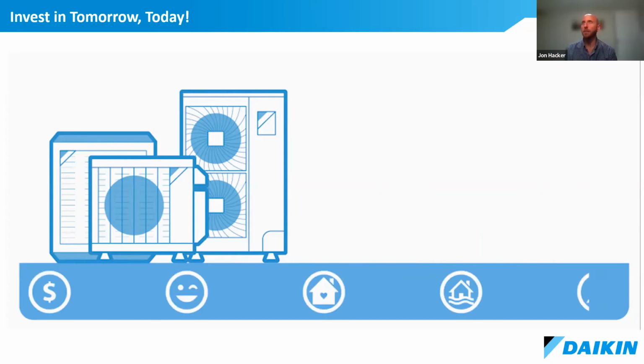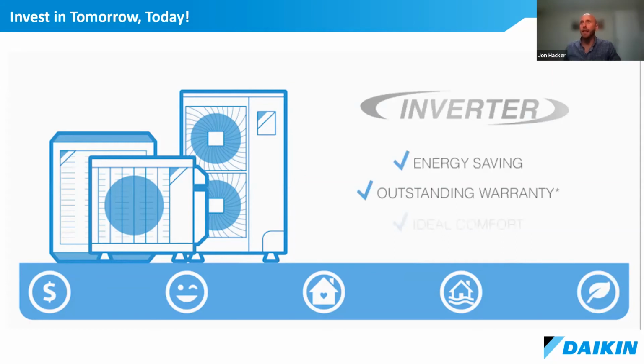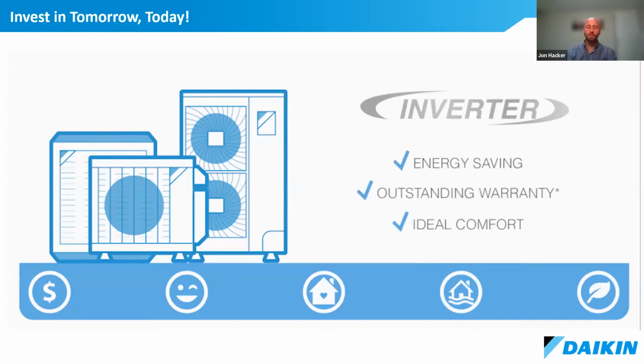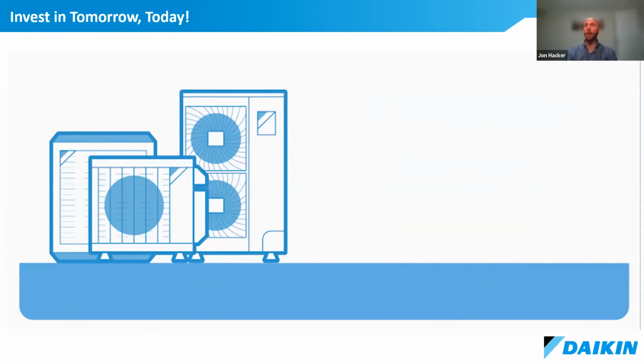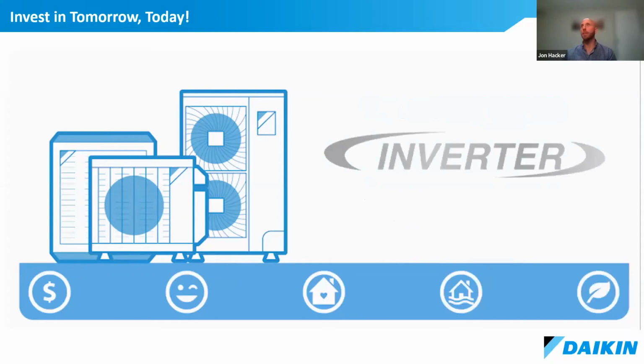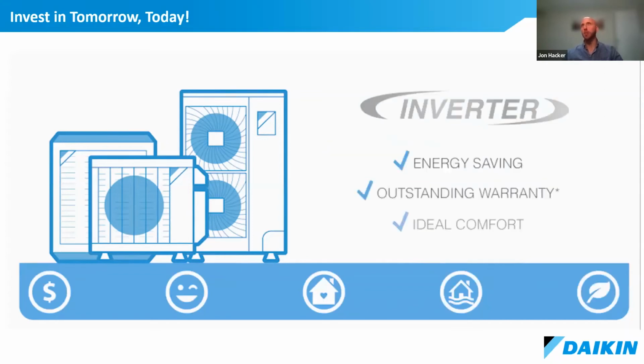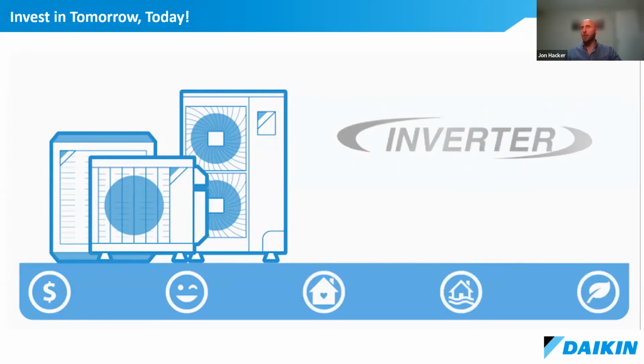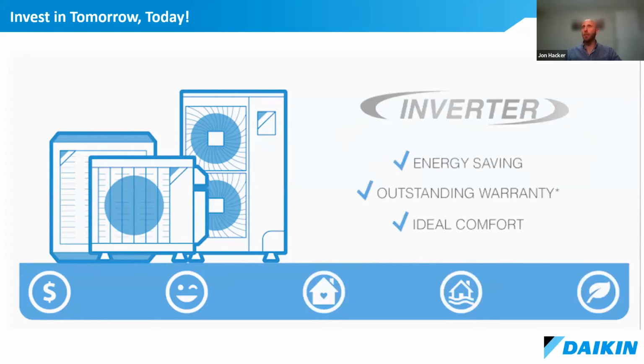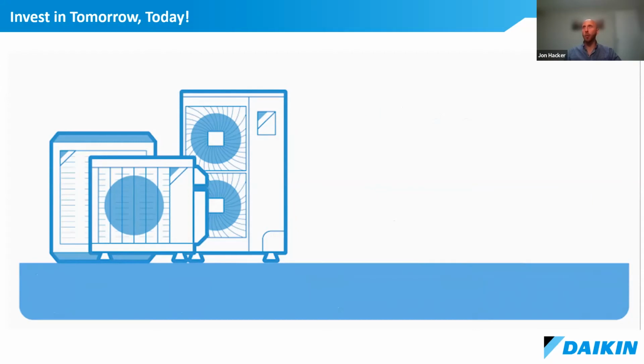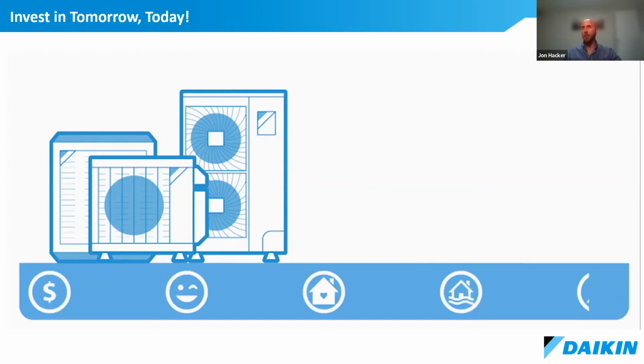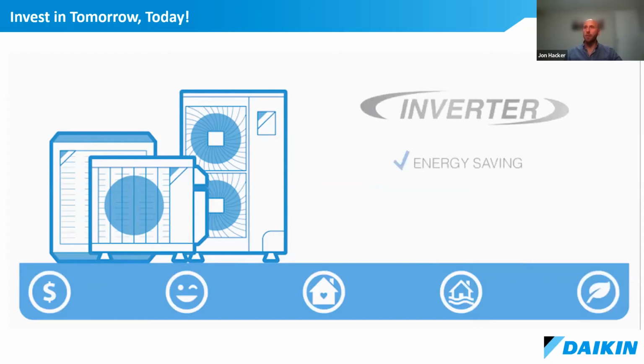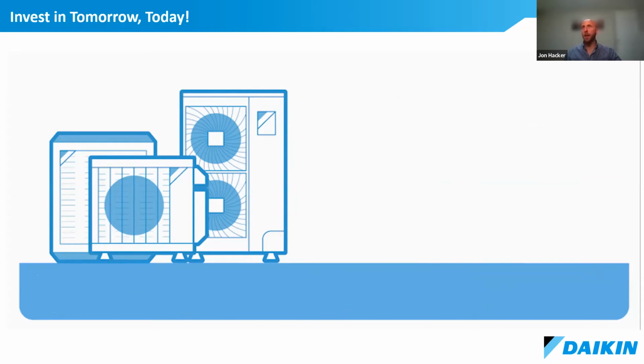the cost for adding an inverter isn't really incredible. A lot of the benefits that we're talking about do require communication between all of the equipment, because it is more complex, because there's multiple sensors, we're reading in more data. So from an install perspective, it can be more complicated to make sure that the systems are wired appropriately, that you have the right electrical in certain places. So there certainly is a cost premium.